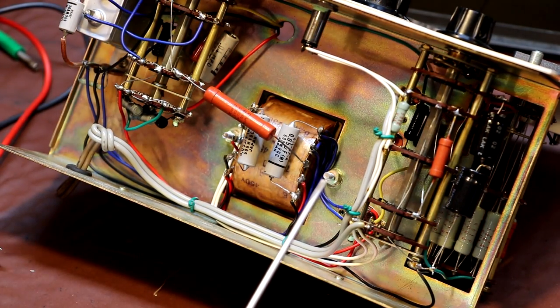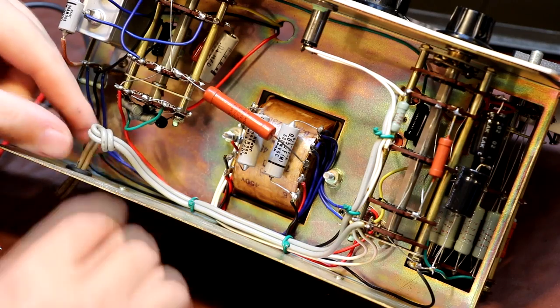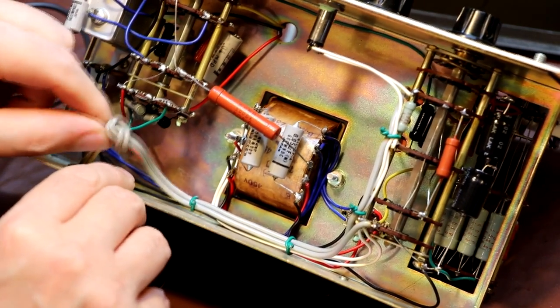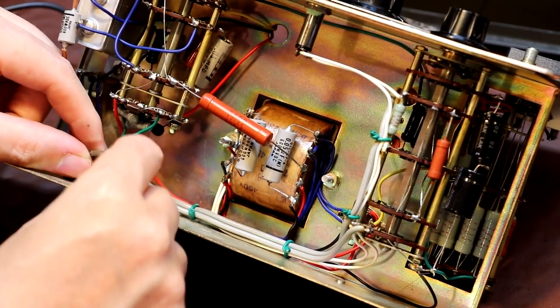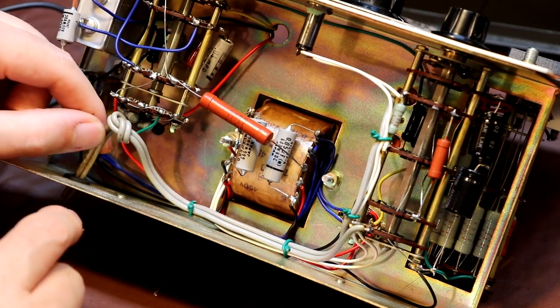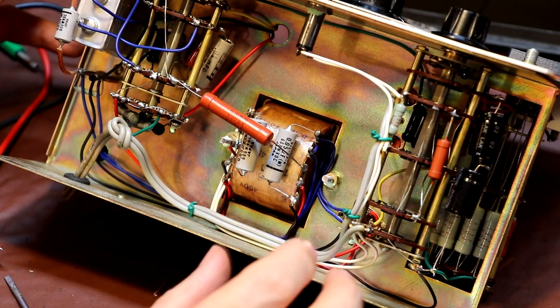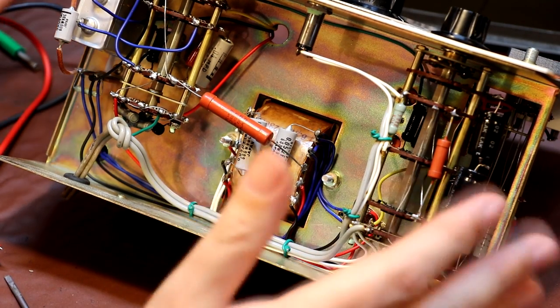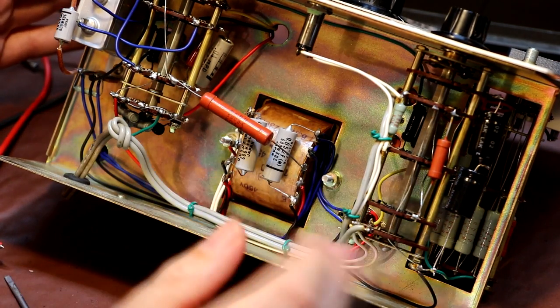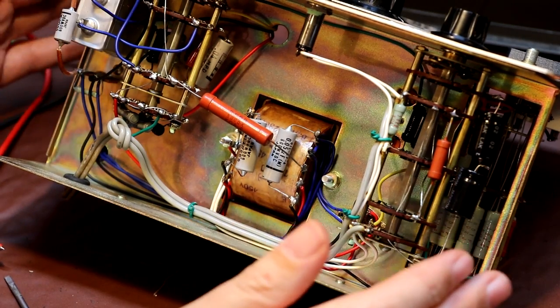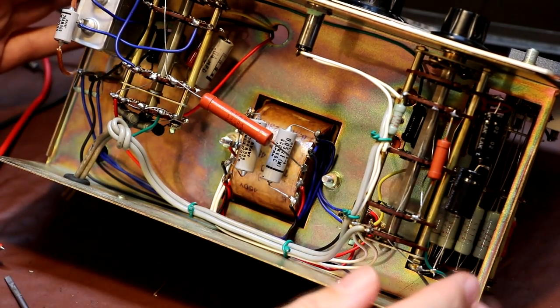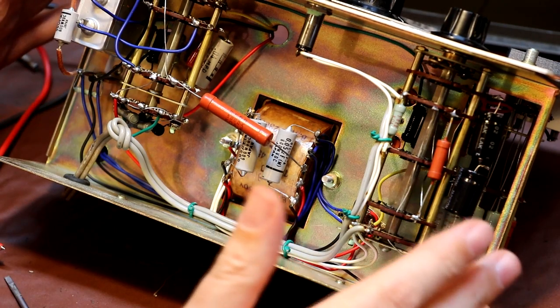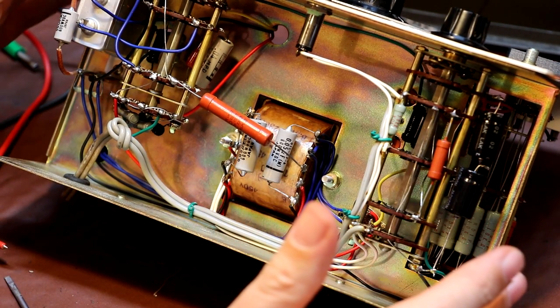So I think one of the first things that we will need to do, and I did mention it earlier, is that I was going to disconnect this 2-core mains cable and replace it with a 3-core mains flex that's actually got an earth in it. And now we have found this problem with this capacitor connected to the chassis, I think it becomes much more important to make sure that the chassis of this equipment is properly earthed before it's powered up.